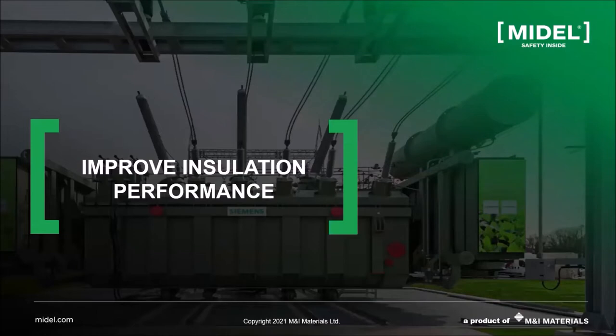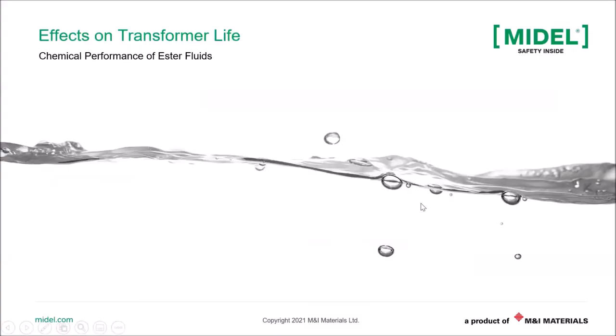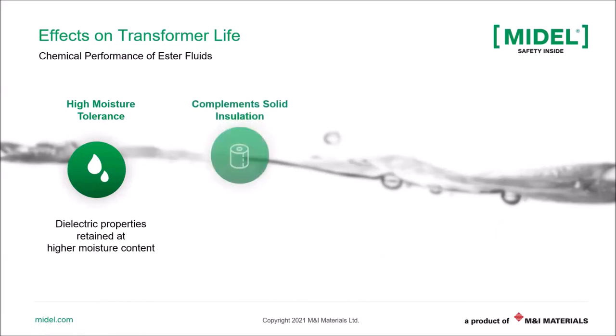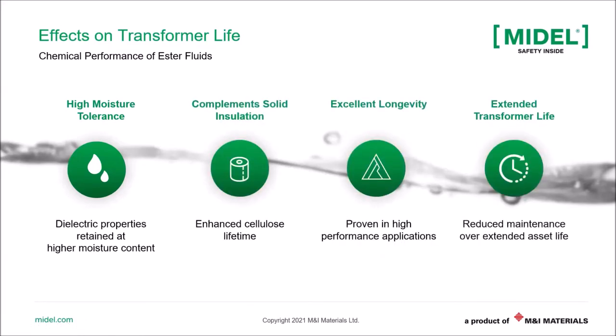So Jinesh is going to now walk you through a little bit deeper about why this particular MIDEL ester chemistry helps improve the insulation performance. Thank you, Anthony. So what you saw earlier on, as far as moisture is concerned, it's very critical to transformers. So transformer design engineers have to make sure that they can address the moisture content issues in different manner, all the way from designing transformers to manufacturing. And then the end users have to also figure out how to maintain those transformers, because moisture is one of the properties that can cause many issues within the transformer.